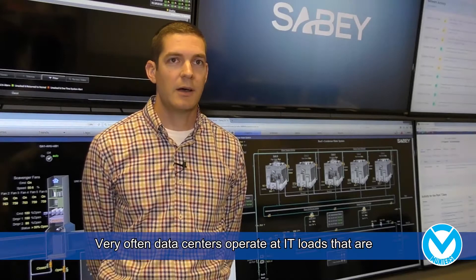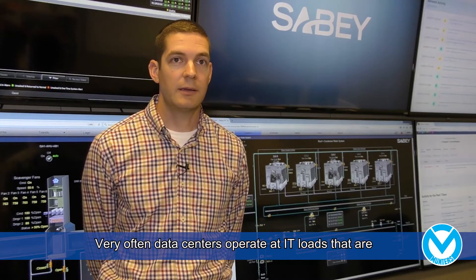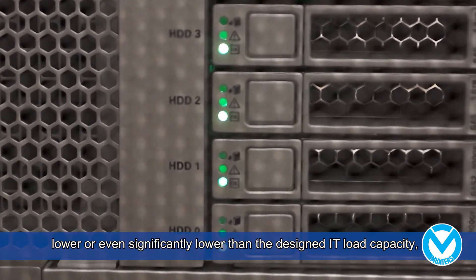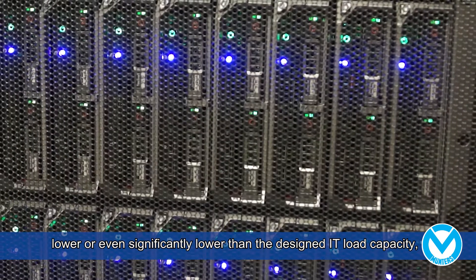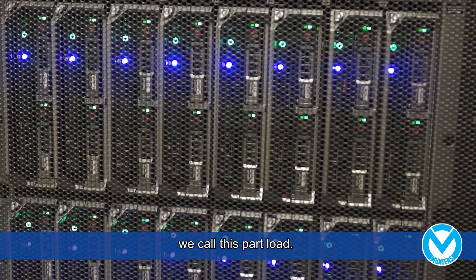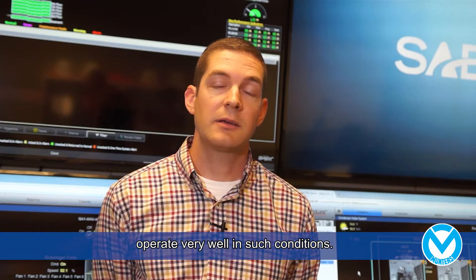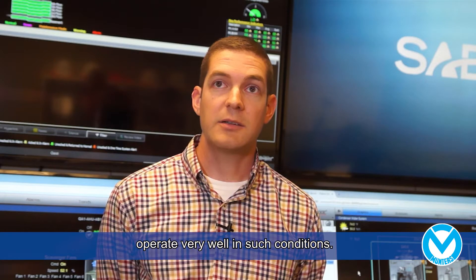I'm Ryan Bebout. I am the operations manager for Sabey Intergate Quincy campus here in Quincy, Washington. Very often data centers operate at IT loads that are lower or even significantly lower than the design IT load capacity. We call this part load. We found that the Munters indirect evaporative cooling units operate very well in such conditions.